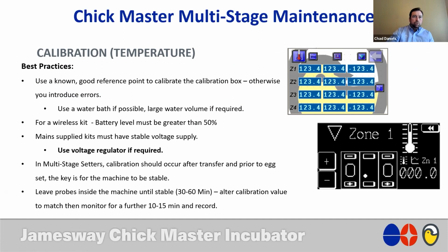and then to put the probes from your calibration device, regardless of whether you're using an RC2 kit or an older suitcase style of calibration kit, you just drop those down into the water. And the main thing that water does for you is, because it's a volume of water, it doesn't change temperature very fast. And so this allows you to verify with your calibration device that all of your probes are reading the same exact temperature. So that's the number one rule in calibration: calibrate your calibrator.